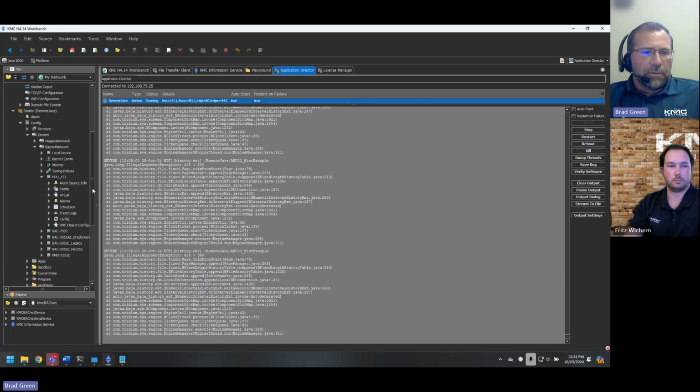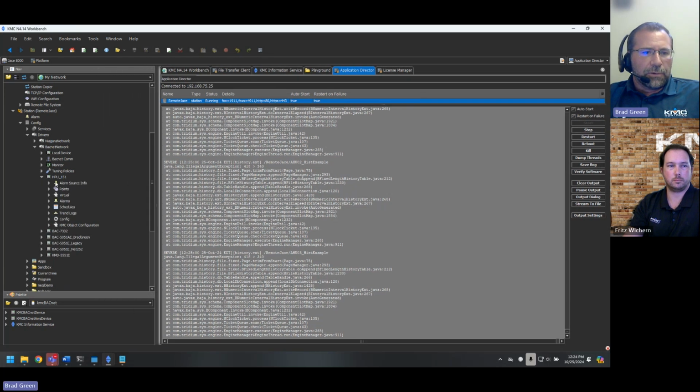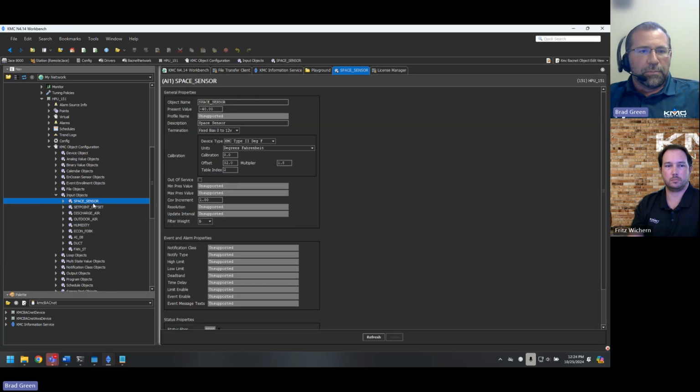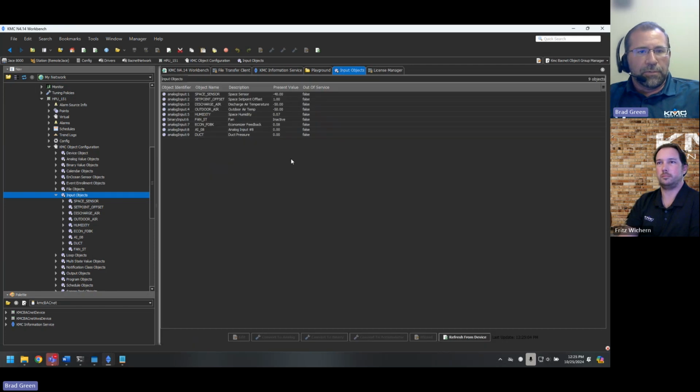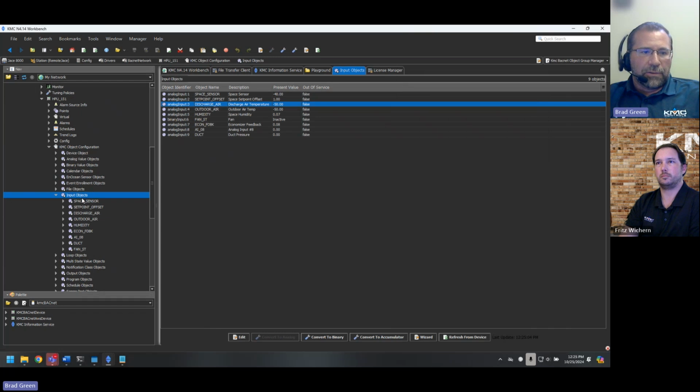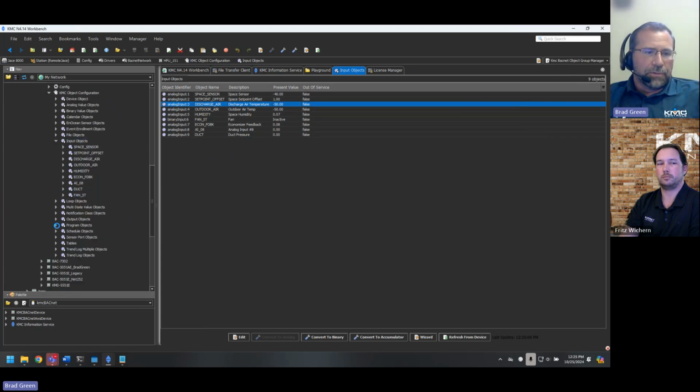So in the previous release of Converge, what we added was underneath this KMC object configuration node, you'd always been able to expand it, but you were never able to expand the input objects. So now you can expand the input objects and click on an individual item to go ahead and make changes there. Before, you had to look at the group view to make changes, select one, and then click edit to make a change. So it's a little bit faster now, easier to work with, but you can actually expand those out.